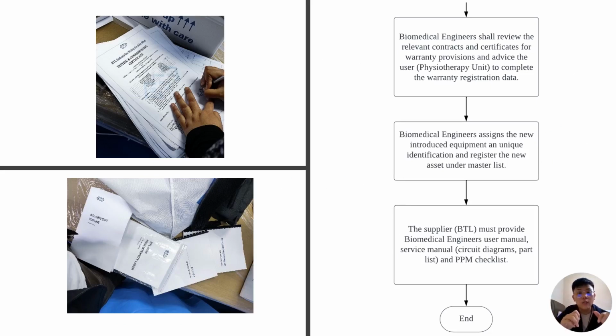the biomedical engineer will review the relevant contract and certificate for warranty provisions and advise the user, which is the physiotherapy unit, to complete the warranty registration data. After that, biomedical engineers will assign the newly introduced equipment a unique identification and register the new asset under the master list. This process will be further explained in the coming slide. The last step is that the supplier, which is the BTL company, must provide biomedical engineers the user manual, service manual, together with the circuit diagram, parts list, and PPM checklist. So this is all about the testing and commissioning of new medical equipment.